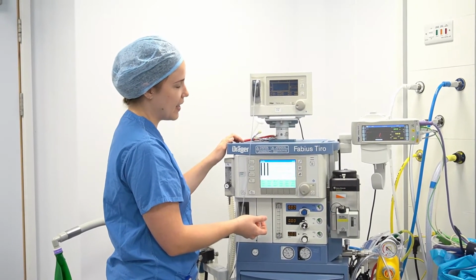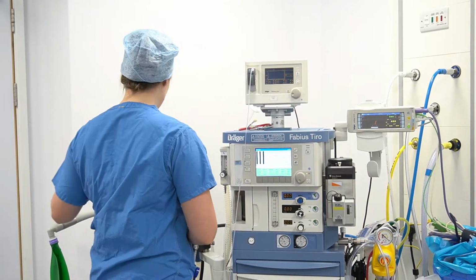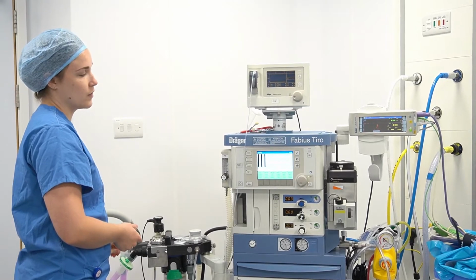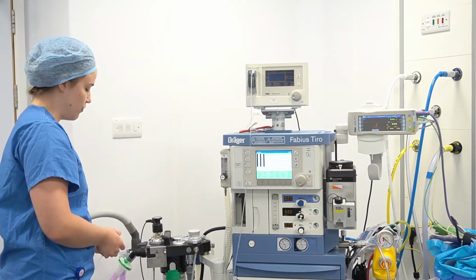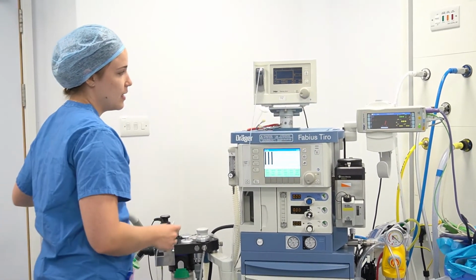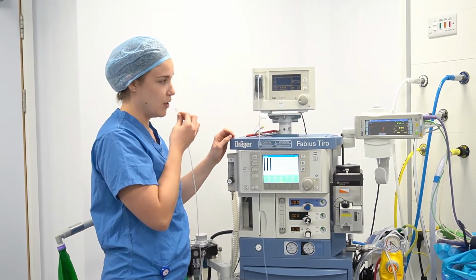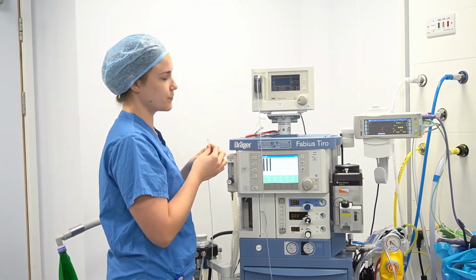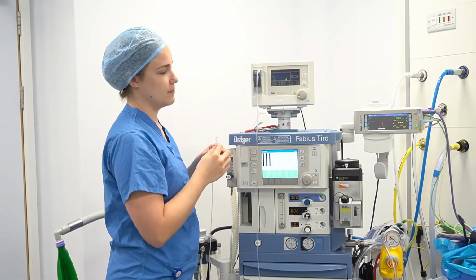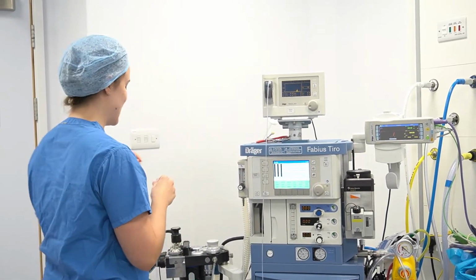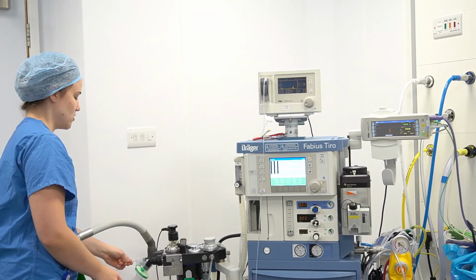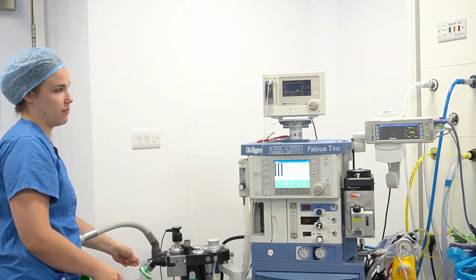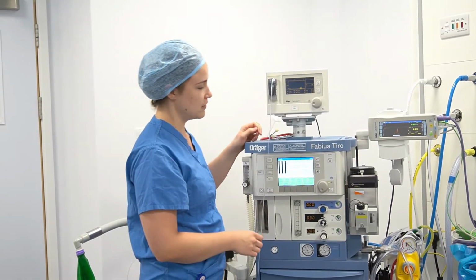Okay. While we have this on now, we'll just check that the CO2 monitor is working correctly by just blowing into the sample gas line. And we can see there's a small CO2 reading there, which will obviously, once the patient is ventilated, become more regular with every respiratory effort.